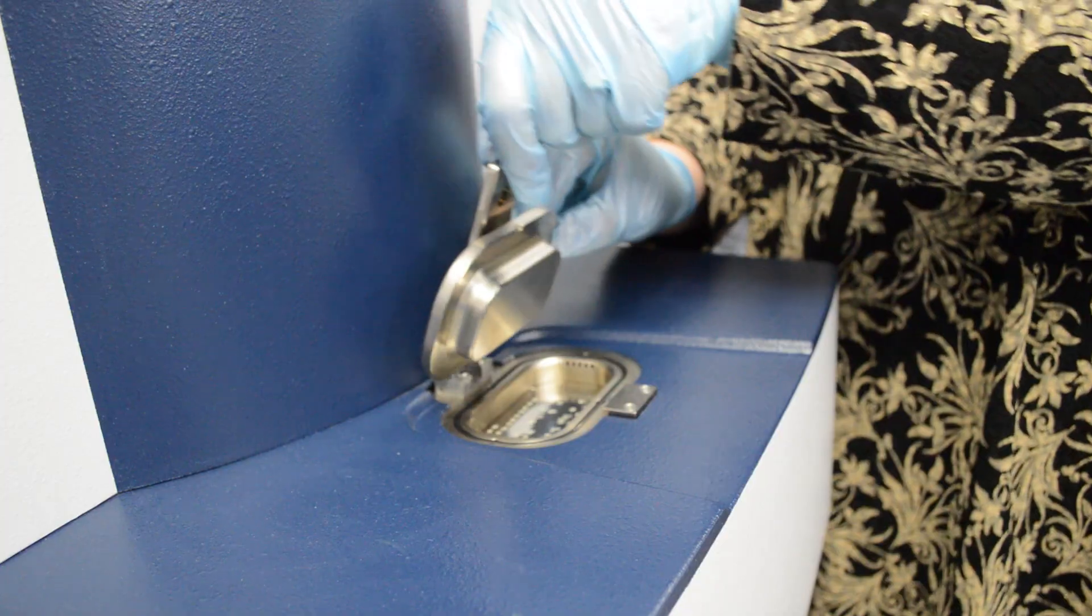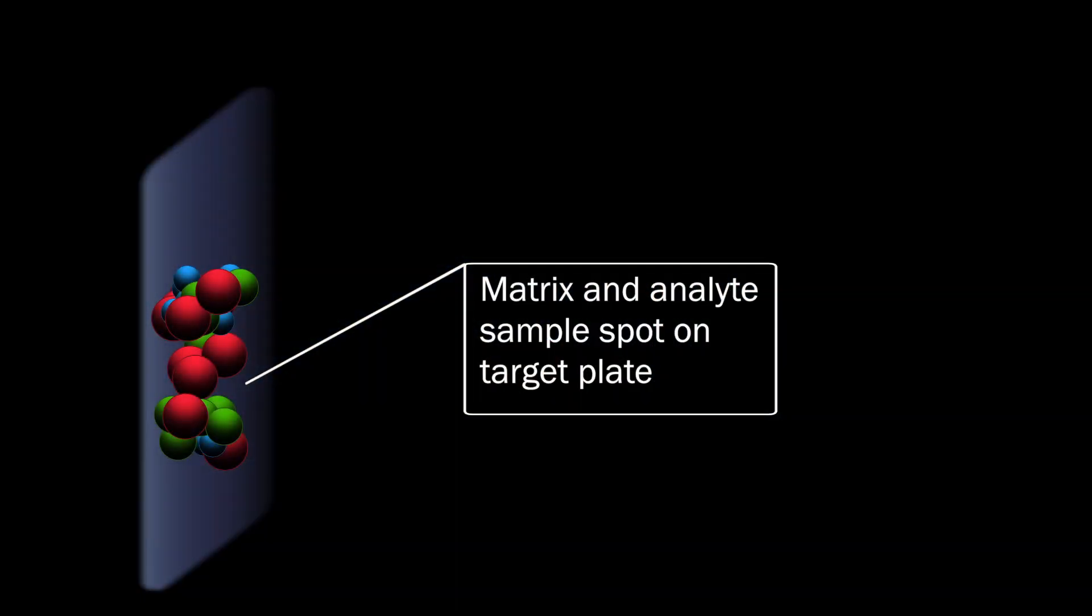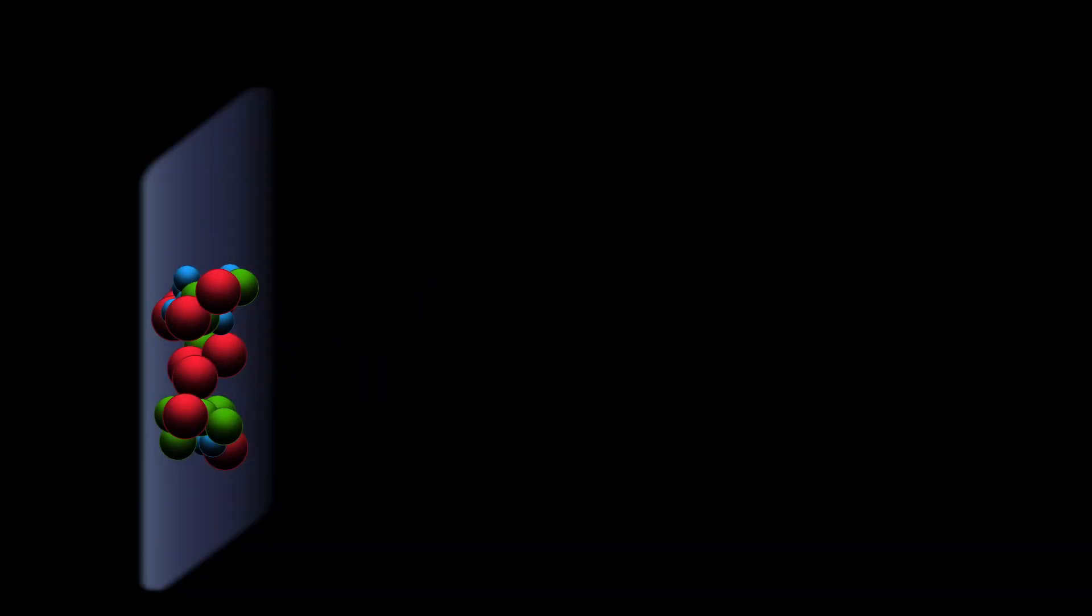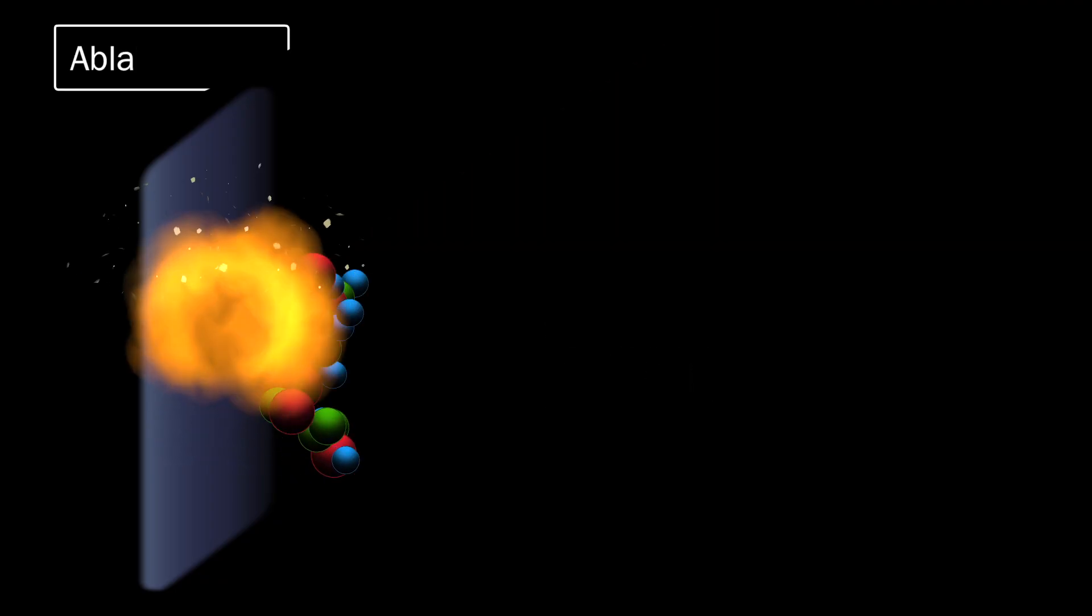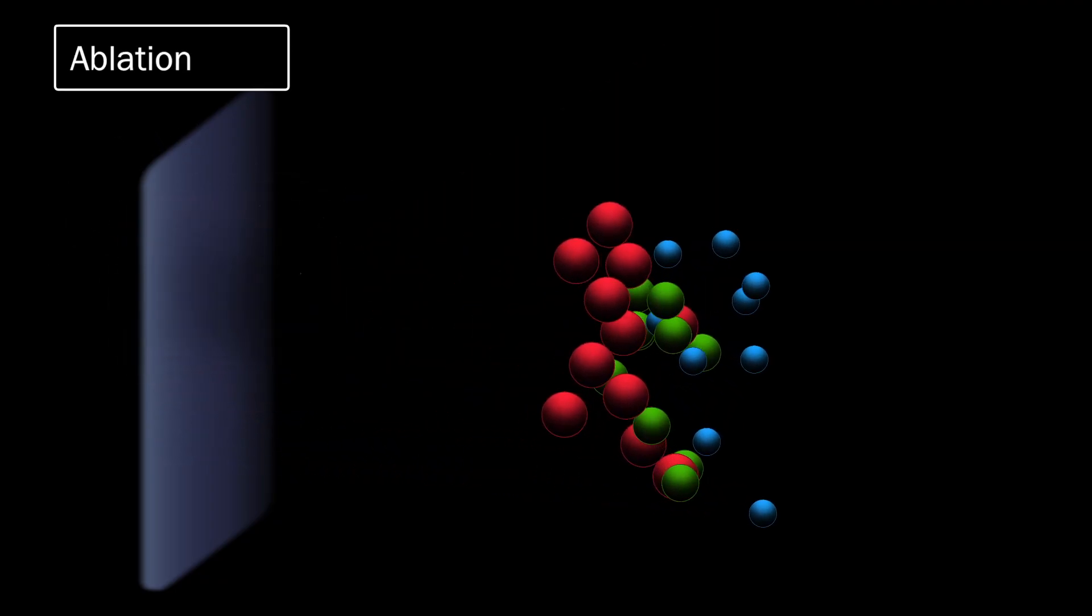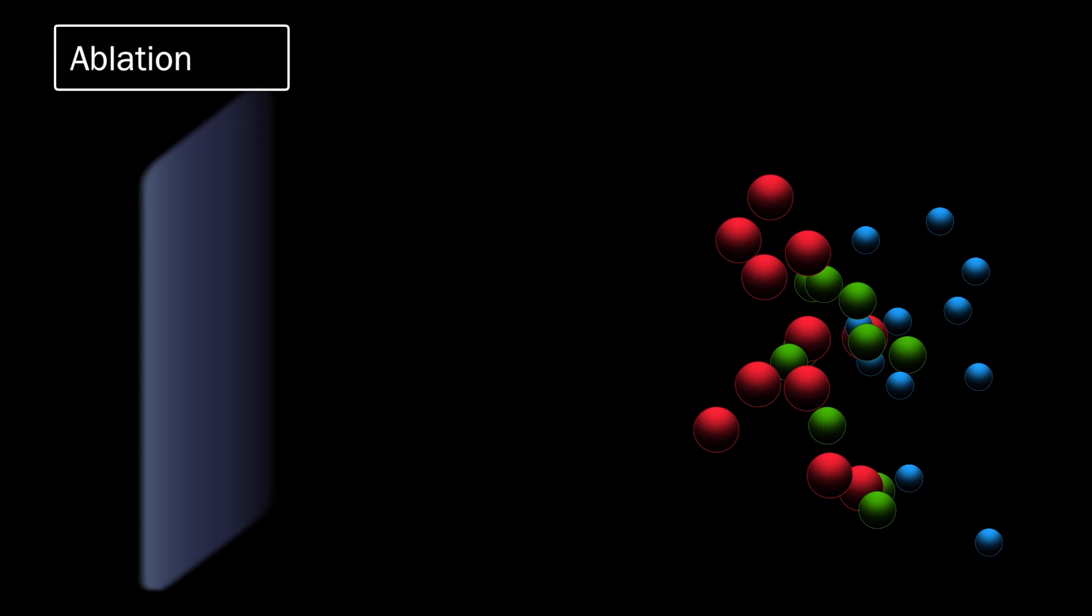Once inside the spectrometer, the target is brought into a vacuum and struck by a pulsed UV laser, usually at a wavelength of 337 nanometers. The laser energy is absorbed by the matrix molecules, which are energetically ablated from the surface of the sample, carrying the analyte molecules into the gas phase as well.